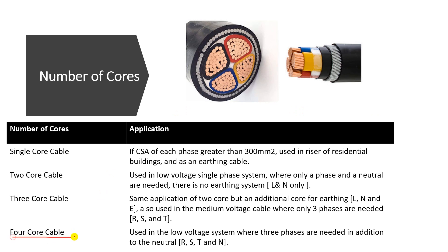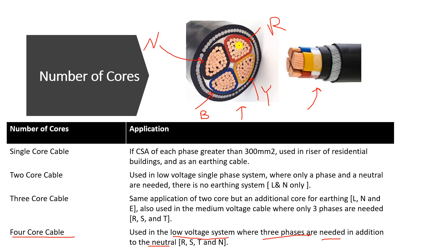The last type is the four core cable. It has three phases and a neutral, so it is used in low voltage systems where three phases and a neutral are needed — R, S, T, and N. You can see red, yellow, and blue for the three phases, and black for the neutral. At the end of the cable, you can separate each core individually to connect them to the bus bars. This is the three-phase and neutral four core cable.